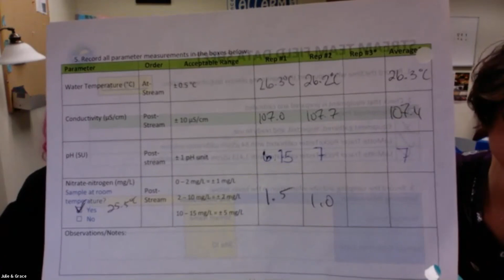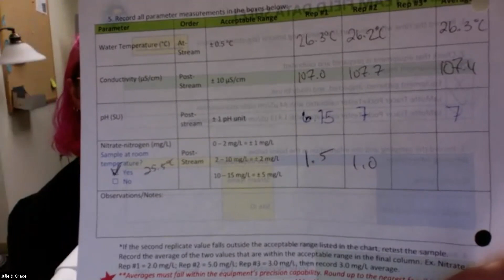Kyra, what's ours? We got a 1 and a 1.5. Can I put 1.25? No, you cannot. Why? Because that is not within the equipment's feasible measurements. You will have to round up to that 1.5. That was awesome. So that's a good example of that little precision bit there.